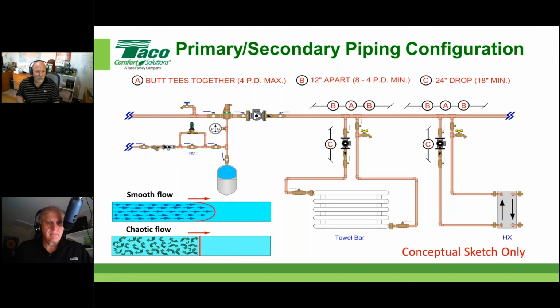As soon as I come out of the circulator, because of the mechanical energy that's being added to the fluid by the circulator, I'm in this chaotic pattern. I'm every which way. But as it goes by a certain amount of straight pipe, it eventually mellows out and becomes smooth. The idea and the concept about the B note here is I want nice smooth flow coming into that first tee. Once I obtain that, I'm already smooth. This circulator moving fluid can disrupt that a little bit, but not as much.